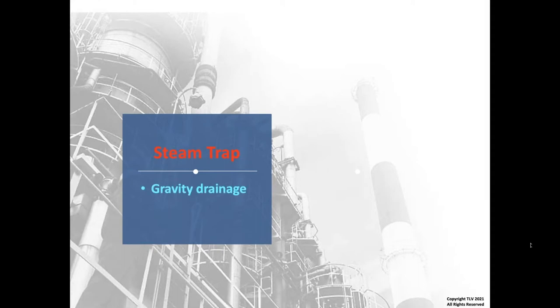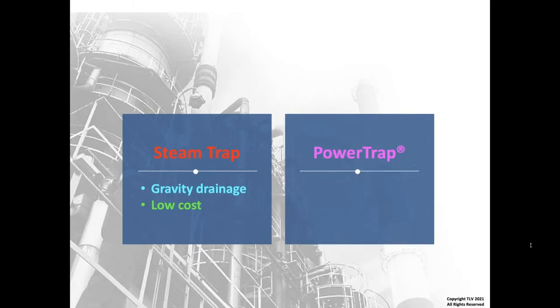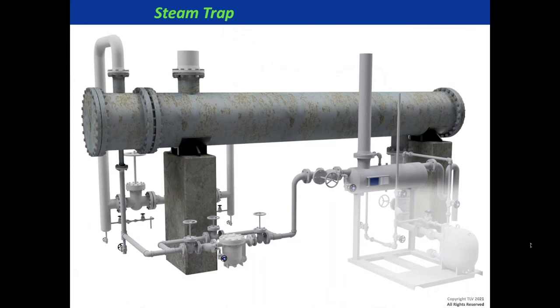One basic consideration is: should we use a steam trap? A steam trap relies on gravity drainage or positive pressure differential — that's the lowest cost option on a capital project and should be used whenever there's positive pressure differential. But when do we need to install a power trap, like a pump trap system, where we have to evacuate with secondary pressure? Here's one process to consider.